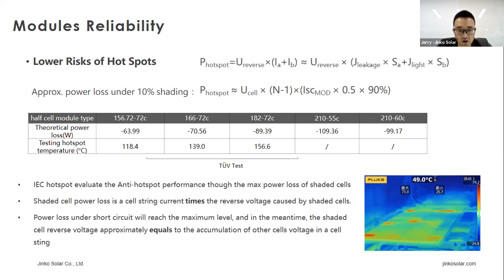Shading is something we cannot avoid for solar power plants, and it is also one of the main causes of hotspots. Once a hotspot happens, that means power loss and performance compromise at your project site. So when you design your project and make calculations and simulations in the PV system for different module types, you need to consider this, because high current means high temperature in the hotspot if shading is unavoidable for your solar power plant.